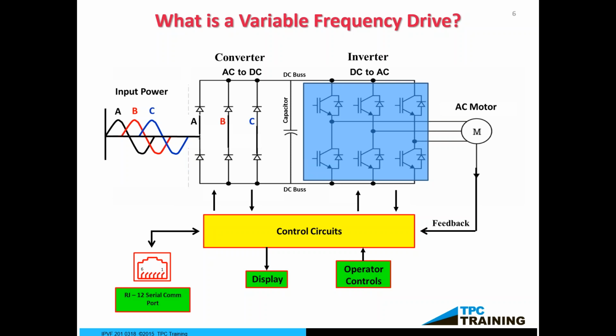If you multiply your AC voltage times 1.414, that'll be your DC bus voltage. So in your troubleshooting, if you want to know the health of the power section of your drive, it's good to know what the DC bus voltage is. So for example, if you had 480 volts on the primary, you ought to have about 680 or 679 volts DC on your DC bus. And we'll be able to get to that DC bus through the display.